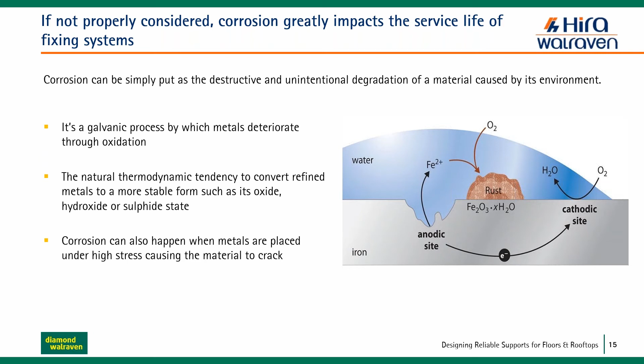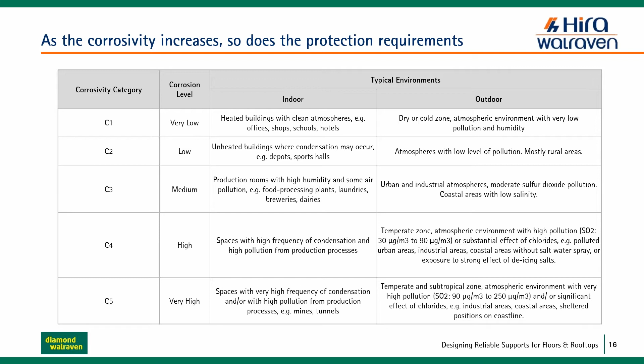Corrosion can happen when metal is placed under high stress, causing the metal to crack. There are corrosivity categories we need to follow in our region: C2, C3 for low and medium corrosion resistant environments, and C4 for high corrosion resistant environments, spaces with high frequency of condensation and high pollution from production processes. This is the outdoor environment happening in our region and most regions. That's why any outdoor installation should have corrosion resistance high enough to resist corrosion category C4 and above. That's why we recommend Ultra Protect surface treatment or hot dip galvanizing.